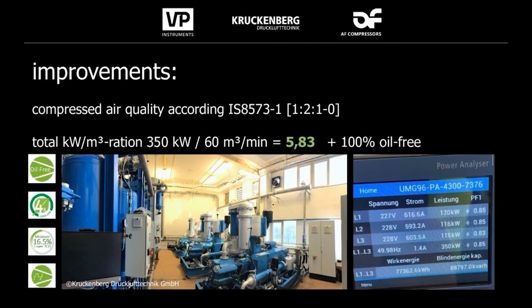All compressors are running, we have to run around, and one guy was sent around to find one single hose which is maybe broken and constantly blowing out air. And they had cases where a 30 millimeter hose was blowing freely in the production because the production was really loud, and nobody was looking at it. And this can be easily detected and monitored with decentralized flow measurements.